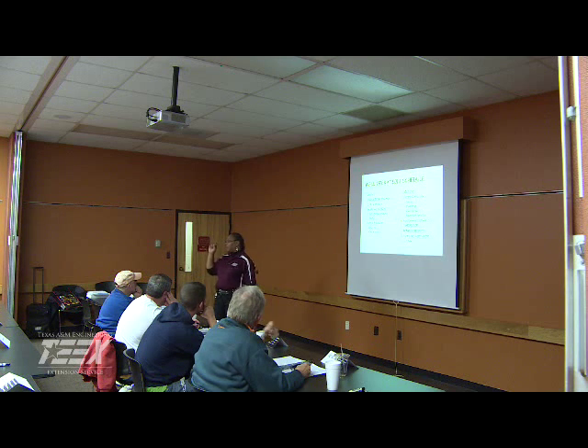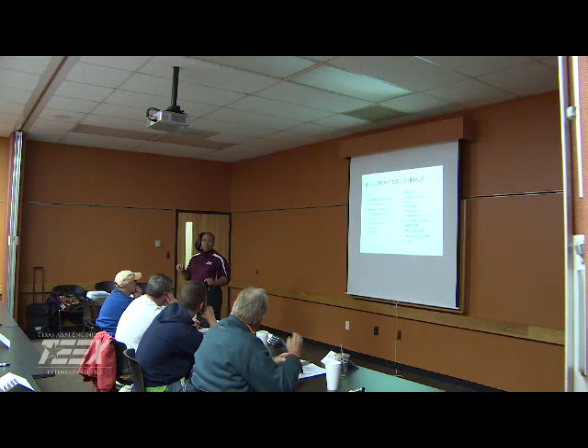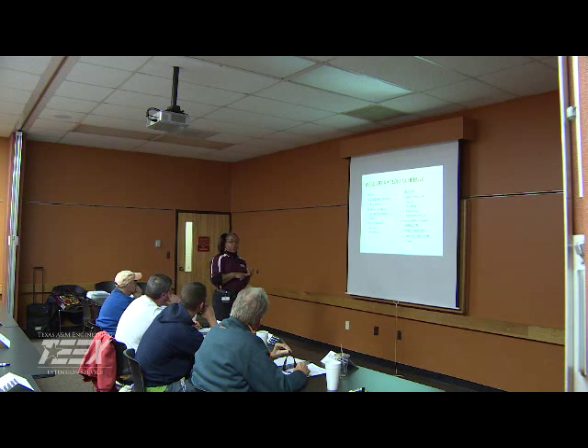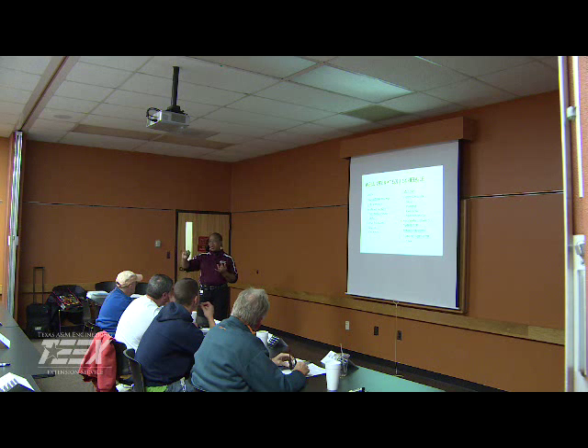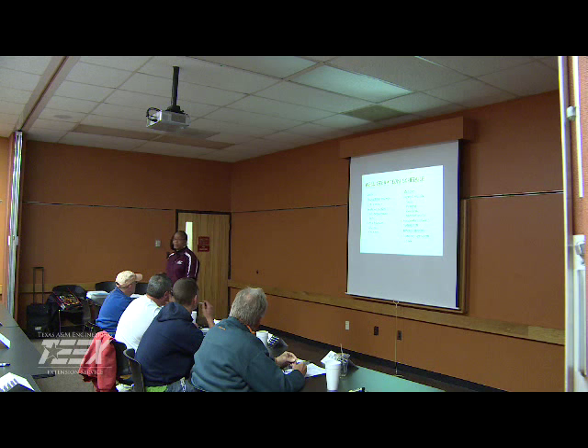Once you have figured that out, you divide that by motor efficiency, and that will give you an electrical or motor horsepower. Then, based on that, how many watts or kilowatts, either one, do we have per motor horsepower? That's another constant. 746 watts or 0.746 kilowatts, and you multiply that by that electrical horsepower, and that will give you power consumption. Multiply by 24, you have it per day. So that's something the operator can do.